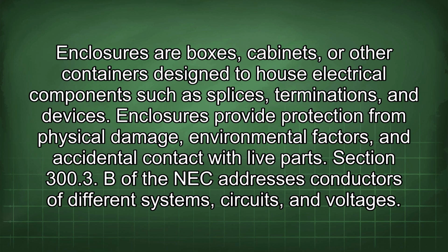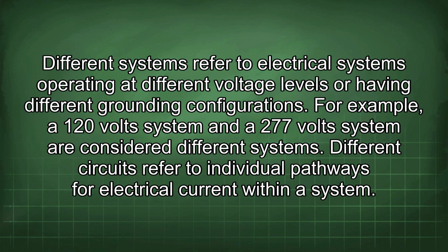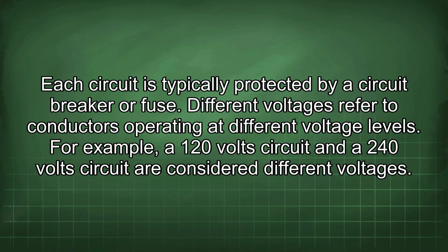Section 300.3 B of the NEC addresses conductors of different systems, circuits, and voltages. Different systems refer to electrical systems operating at different voltage levels or having different grounding configurations. For example, a 120-volt system and a 277-volt system are considered different systems. Different circuits refer to individual pathways for electrical current within a system. Each circuit is typically protected by a circuit breaker or fuse. Different voltages refer to conductors operating at different voltage levels. For example, a 120-volt circuit and a 240-volt circuit are considered different voltages.